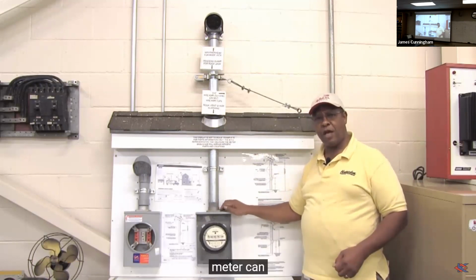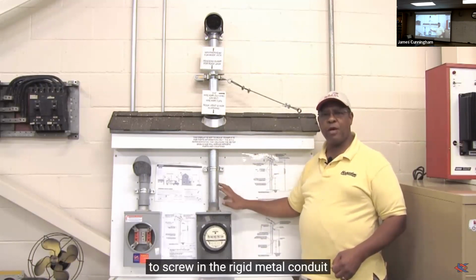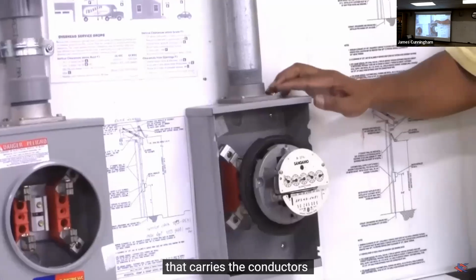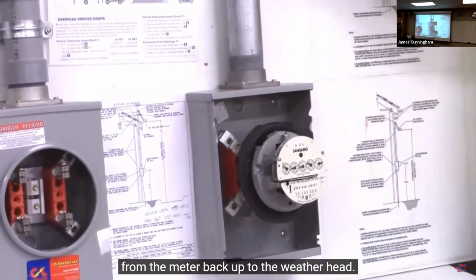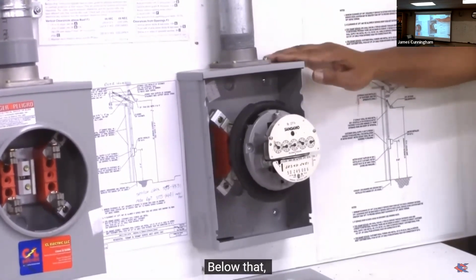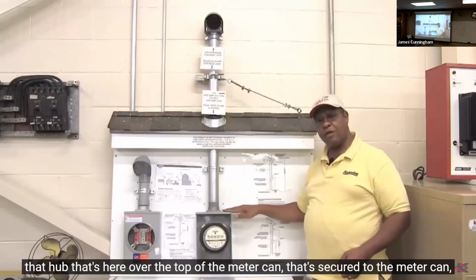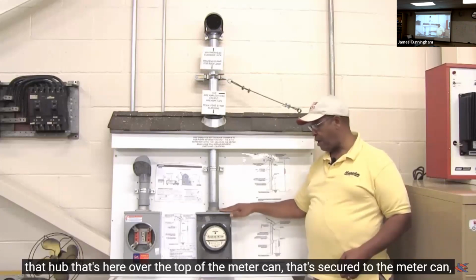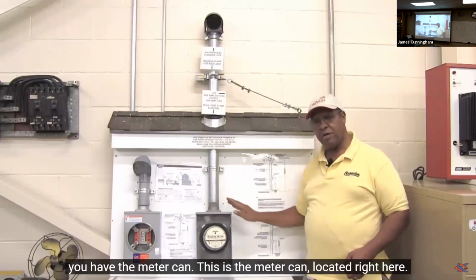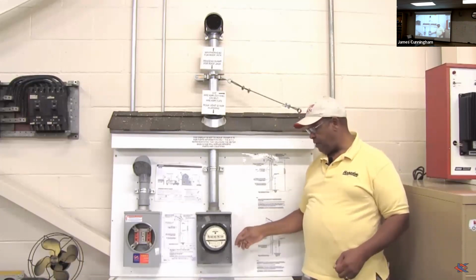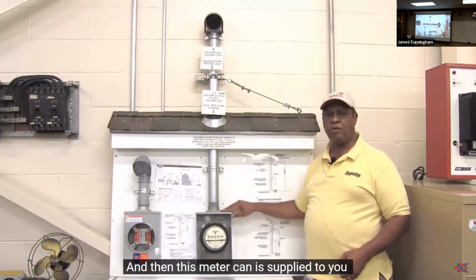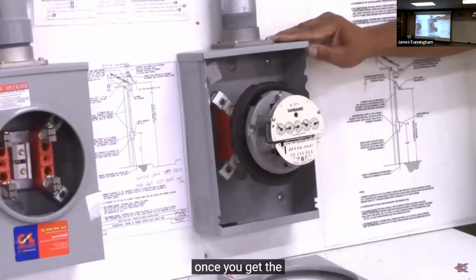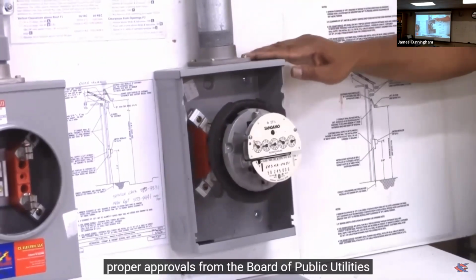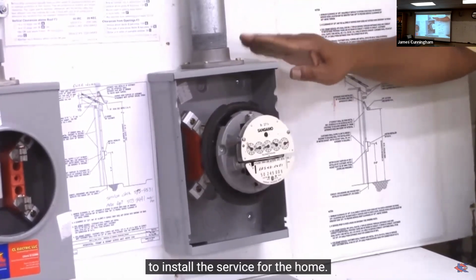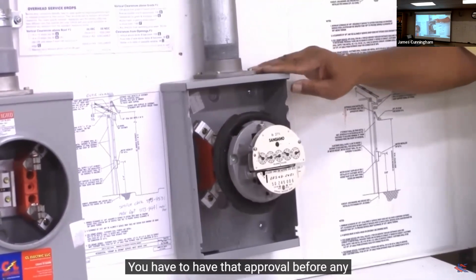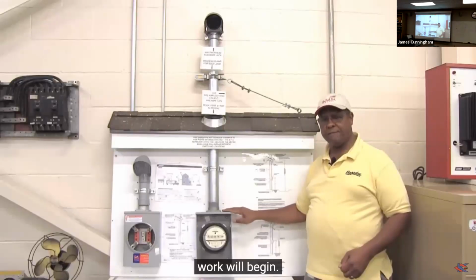And then from that point downward, you'll have a hub, and that hub is a connection at the top of the meter can to screw in the rigid metal conduit that carries the conductors from the meter back up to the weatherhead. Below that, that hub that's over top of the meter can and secured to the meter can, you have the meter can. This is the meter can located right here. And then this meter can is supplied to you once you get the proper approvals from the Board of Public Utilities to install the service for the home. You have to have that approval before any work will begin.